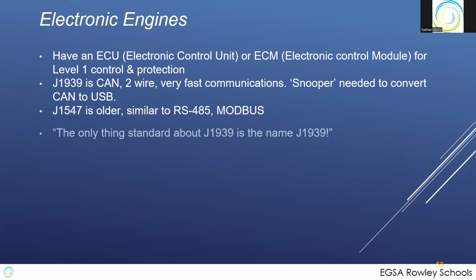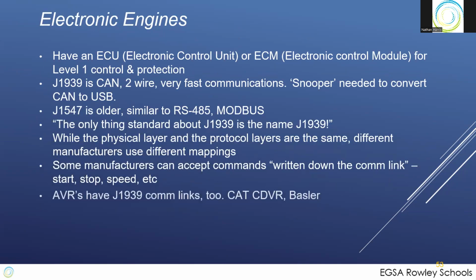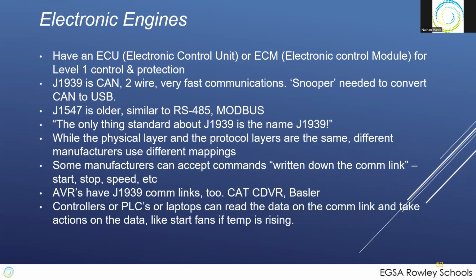Today's electronic engines can actually put a lot of this stuff together into one ECU. I know that Cat's got some, Cummins has some, that put all these level 1, 2, and 3 controls all in the ECU. It works. There are pros and cons to using proprietary controls versus unlocked and open platform controls. It depends on who's servicing them and how, quite often. Availability of service people. If it's a proprietary control, it's locked behind a password. Your choice for heavy troubleshooting and heavy tune-ups is really limited to those that have the password, which tend to be the manufacturer's service people, and that tends to be expensive in some cases, or impossible to get if you're sending them overseas sometimes.